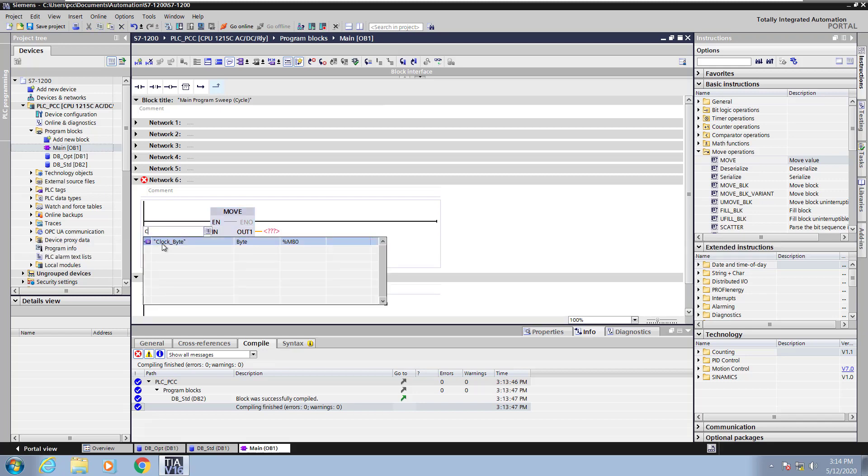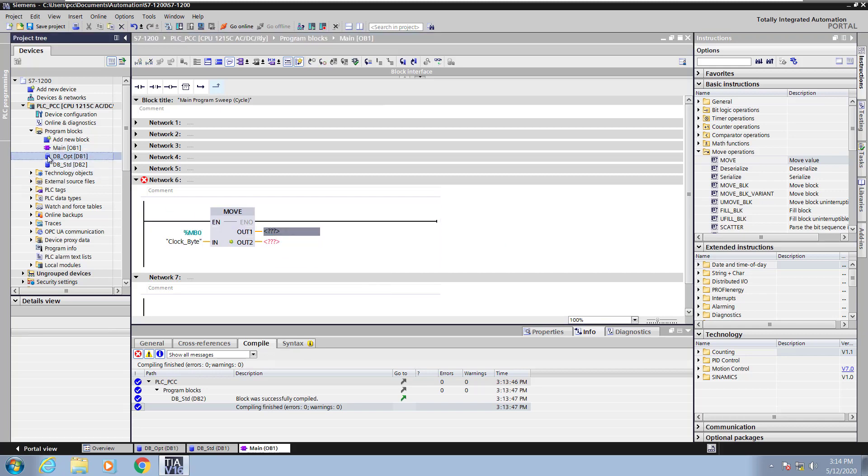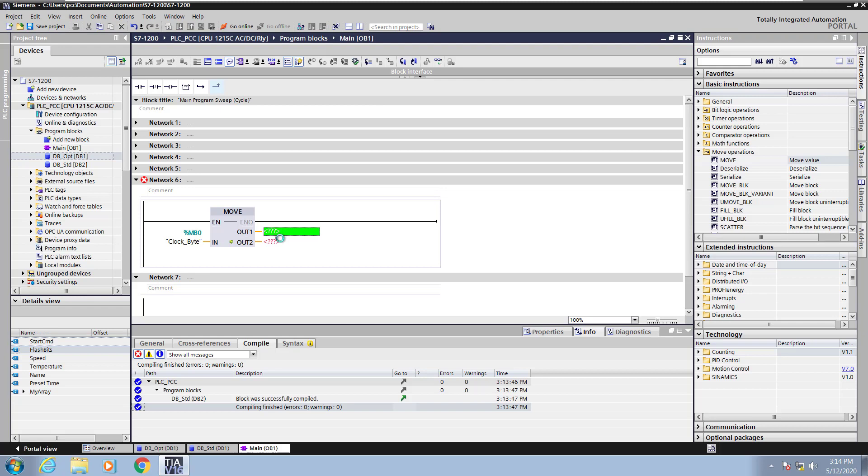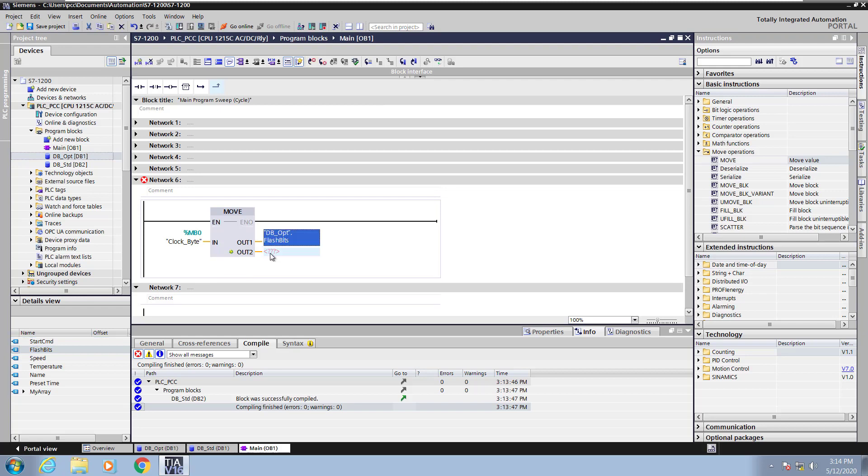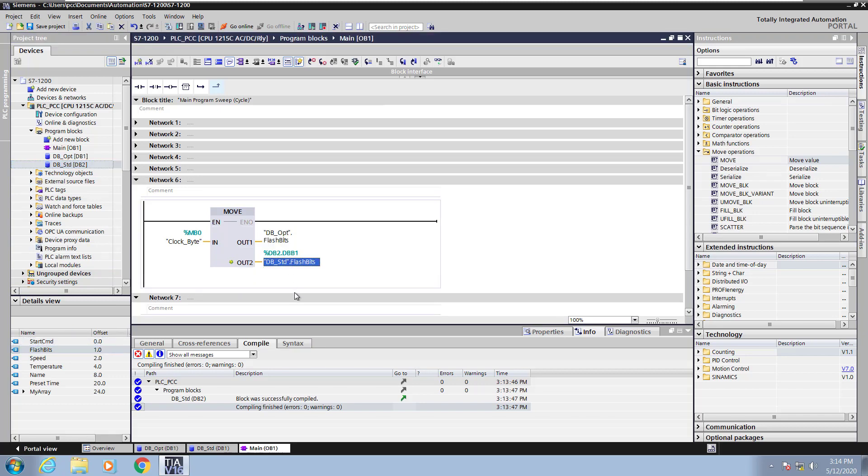On the input side I'm going to select the clock byte that we defined earlier and I'm going to move that into a data block address. So I'm going to highlight my optimized data block address and I'm just going to use the drag and drop method. So I'm just going to drag flash bits from the details view in and then you can see the optimized access. Now I'll highlight the standard access block and do the same thing for the flash bits from the standard data block. So you can see the difference between the addressing between the two.